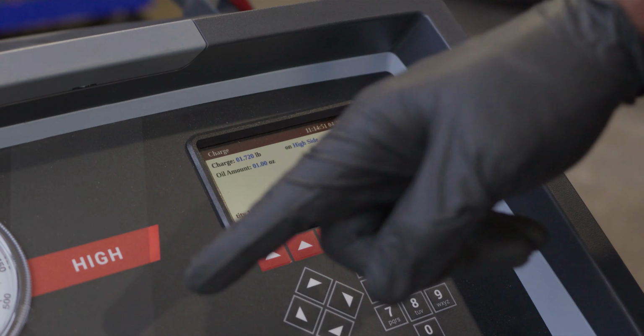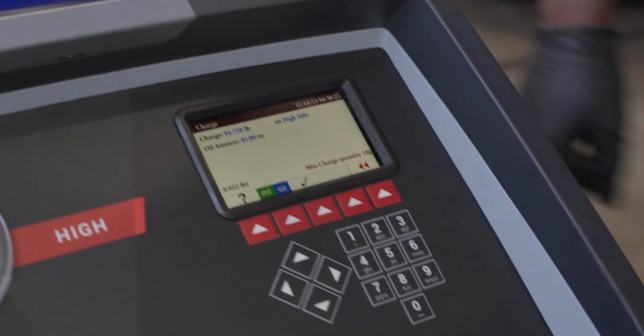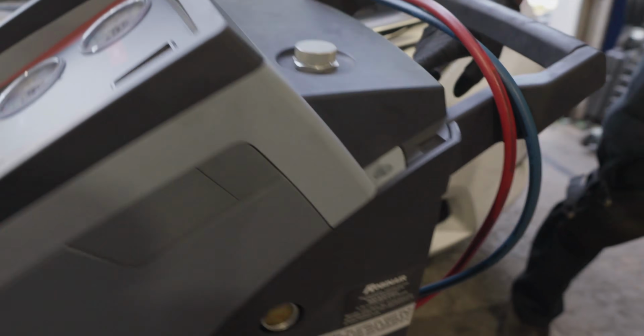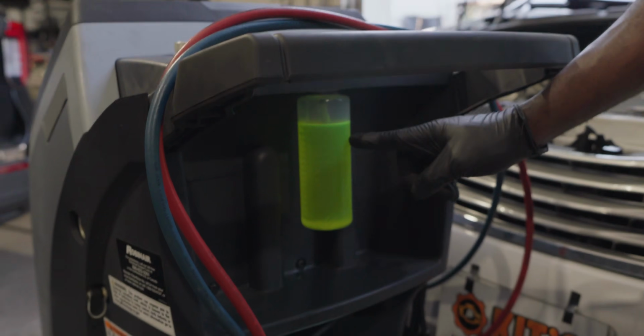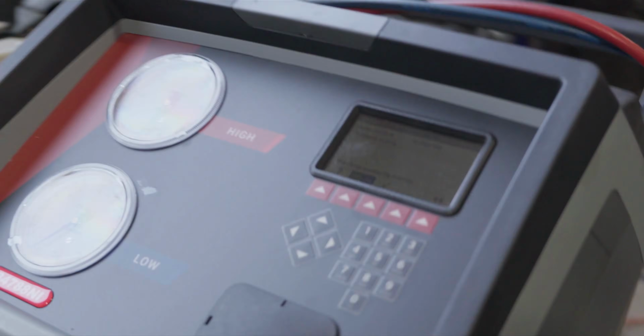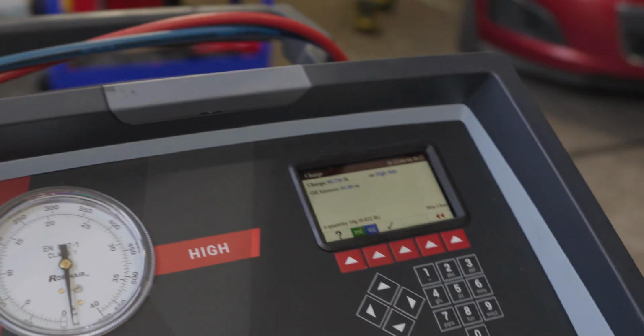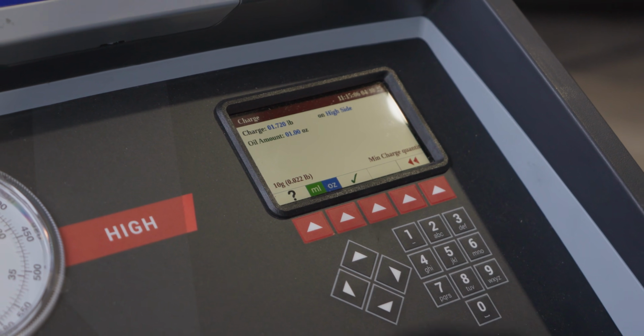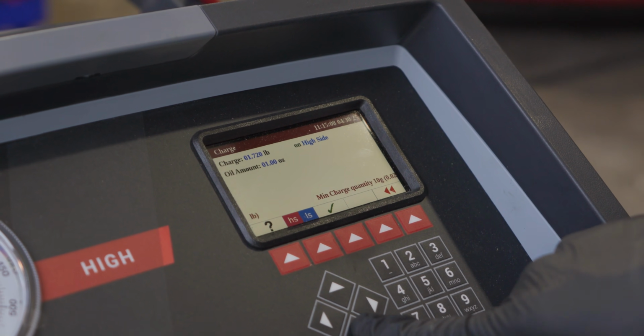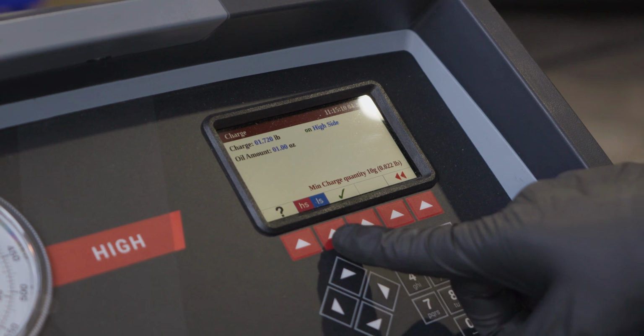Now the oil we're going to put in is dyed. Kyler, can you show this bottle here? This is dyed refrigerant oil, as you can see it looks green. So if there's a leak somewhere, that oil is going to leak where the leak is, and it's going to allow us to see the leak easily.